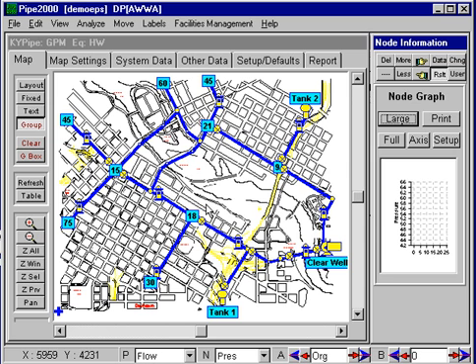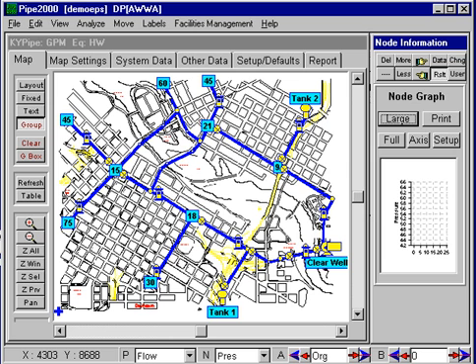The normal or baseline data for demands are shown here. For example, the demand here is 21 gallons per minute — this is like the average daily demand. In extended period simulation, we normally will put in a demand pattern which will vary these demands hour by hour based on the usage.